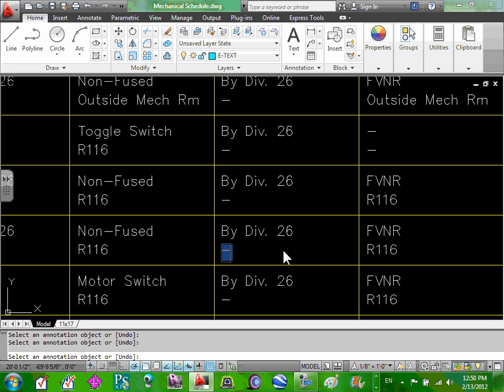Page 6-4, under 200 volt, 208. The first column will give you 3 horsepower, right? I need 2, so I can't go to 1.5, it's too small. So I have to go to 3 because 3 is bigger than 2, right? And then it's 0. Everybody knows why I get that one, so I'm going to go with 0. So this is what I typed in, NEMA 0. That's all you have to do. Type NEMA 0.